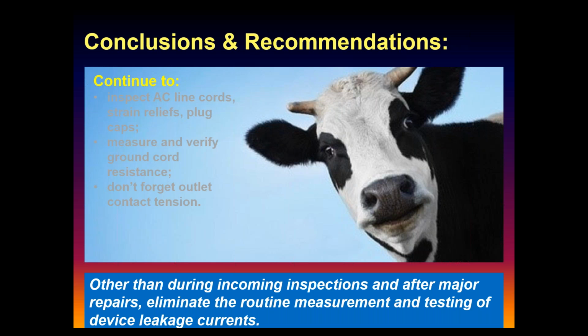All the ORs have line isolation monitors built into the room, which, if you elaborate on that - because other places, for a while, we'd have to go out and chase an extension cord into a hall somewhere just to perform the leakage current test. Yeah, and there's no reason to do a leakage current test in an OR - the whole room is on a line isolation monitor. The reason the isolation monitors are there is that it's what we call a predictive monitor.